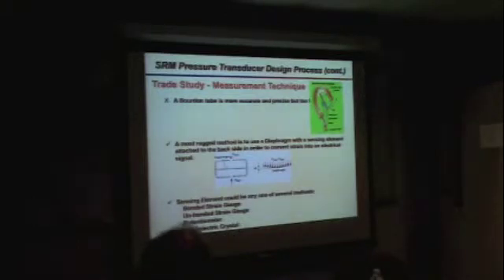So first thing you want to do is a trade study. What type of mechanism are you going to use? So first we would look at a Bourdon tube, because it's highly accurate and precise. This is what a typical Bourdon tube looks like. But unfortunately it's too fragile. It wouldn't withstand the environment. So therefore a most rugged method would be to use a diaphragm with a sensing element attached to the back side. So the sensing element could be one of several methods: a bonded strain gauge, an unbonded strain gauge, a potentiometer, or a crystal.